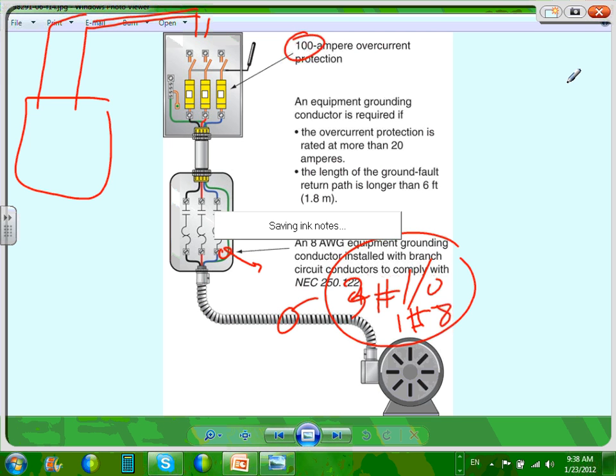So for grounding and bonding, just to clarify. Go ahead. The motor has to be grounded, right? Mm-hmm. Are you running the conductor through it? Yep, right here. Oh, I see. You see that green here? Yeah. It's a 3-phase only. So that conductor is a ground, not a neutral.